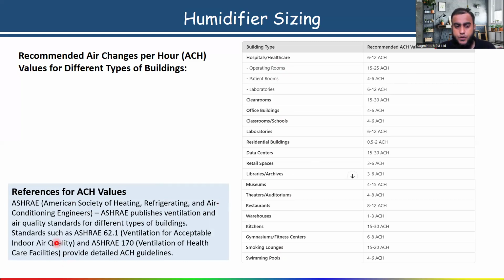So here, see, the reference is given, ASHRAE, American Society of Heating, Refrigerating and Air-Conditioning Engineers. ASHRAE publishes ventilation and air quality standards for different types of building, standards such as ASHRAE 62.1. It is the ventilation standard. When you open this ASHRAE 62.1, you will get this value. And for healthcare facilities, we have ASHRAE 170. In ASHRAE 170, the recommended ACH value is given for each and every type of room.